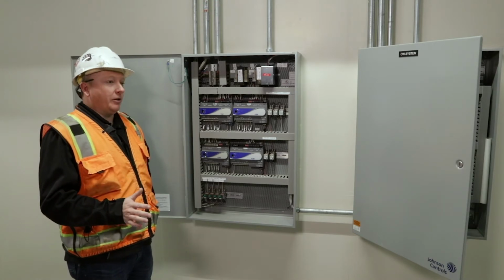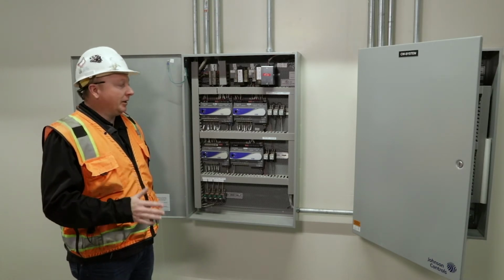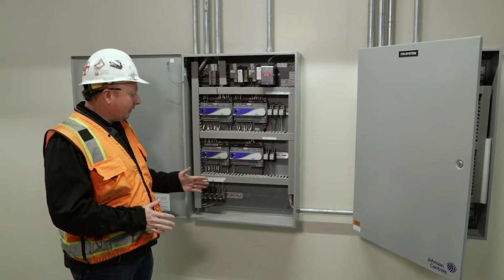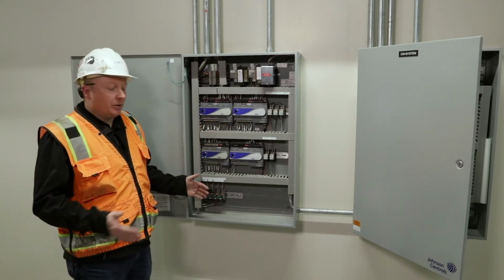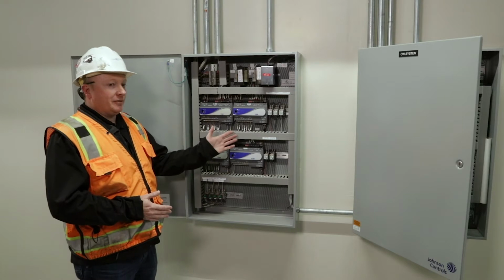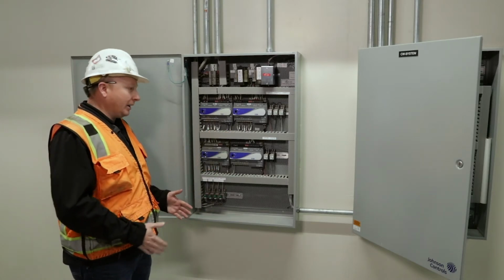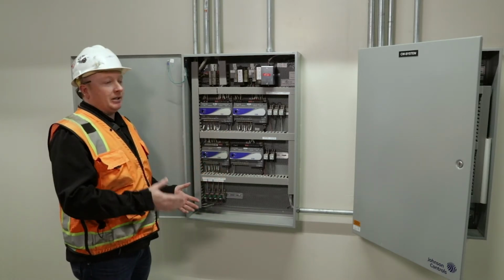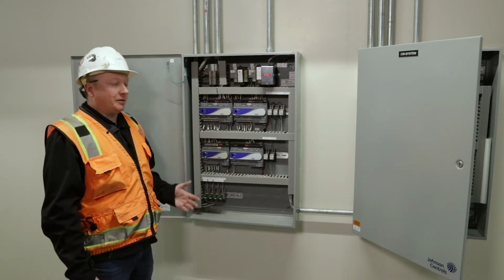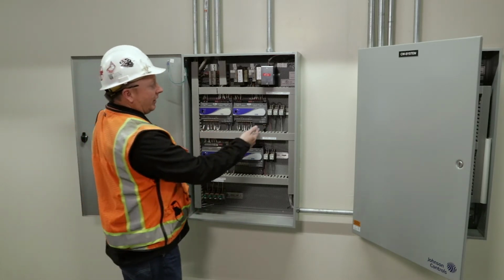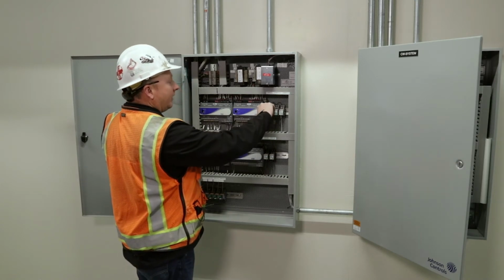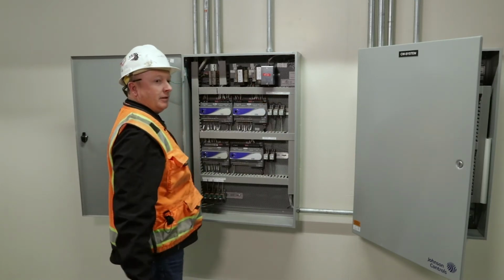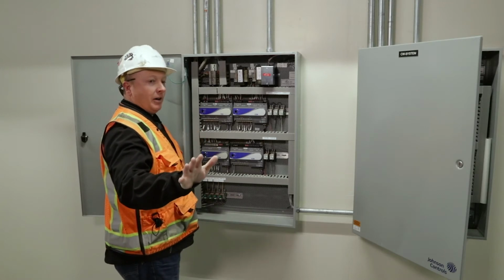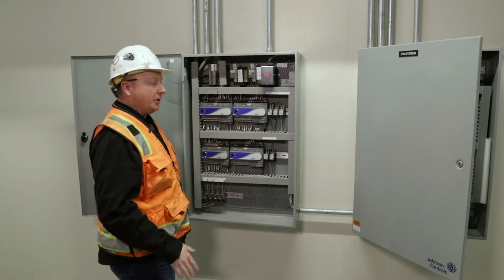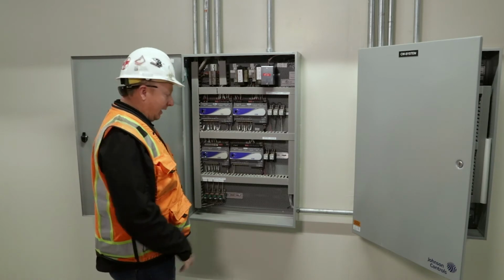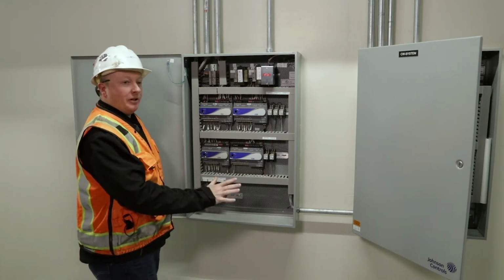So if you want to start those pumps manually, the easiest way to do it is coming over here to this panel. All of our commands, just like at Morse Avenue, we brought to relays before they go out into the field. So you should be able to come to these control panels, and if you need to manually open any isolation valves or start any pumps, you can walk over here, and this is for chill water pump 1. You can flip the relay on, and the pump starts. You don't have to go over there and try and jumper out the starter because there's no HOA. You can just do that, and that's for all the commands that come out of both of these panels.